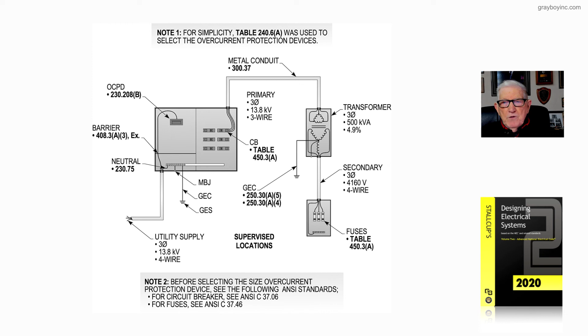But notice now for the components, for high voltage, we would go to Article 490 to select those. And again, in notes 1 and 2, we're explaining that we're using Table 240.6A to select the size of our protective devices, instead of using note 2 and using the ANSI C series 37.06 or .46, depending on if it's a circuit breaker or fuse.